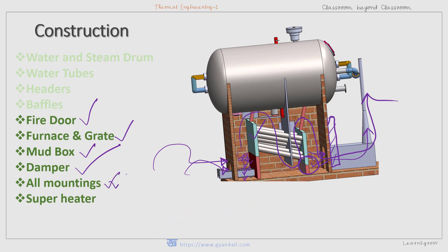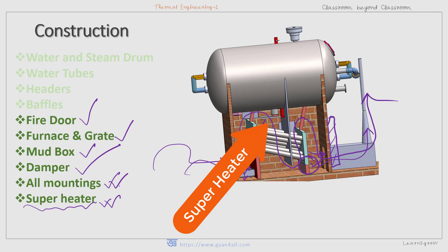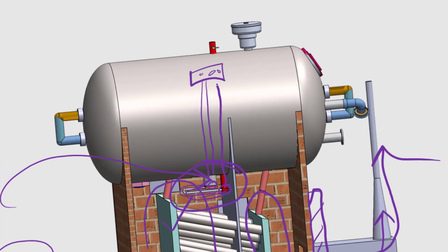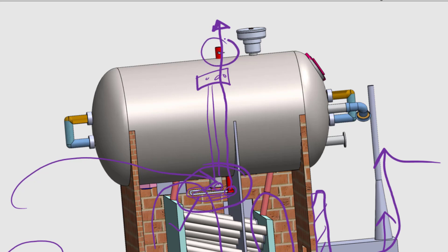The Babcock and Wilcox boiler should have all mountings attached for safe operation. There is also a superheater, which is an arrangement to produce superheated steam. Steam is collected and passed to one header through a pipe, then through a series of tubes which receive heat from the furnace or combustion chamber, and is collected in another header. This steam is then taken to the turbine or the required place through the steam stop valve.